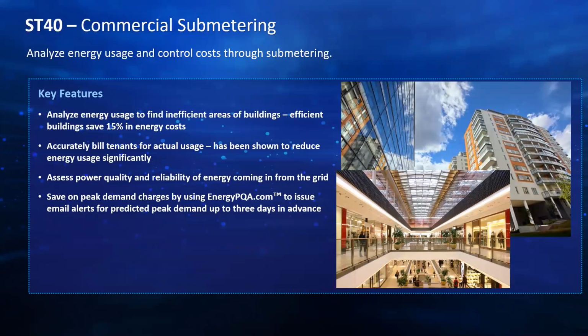Commercial submetering applications. If you have a facility with multiple tenants, you can monitor each tenant and bill them for energy use directly. This has been shown. If people have to pay for the energy used, they will be more likely to use less energy. Shut off lights at the end of the day, shut off equipment at the end of the day, only use equipment when it's necessary and not whenever, because now they're actually paying for the operation of that equipment.